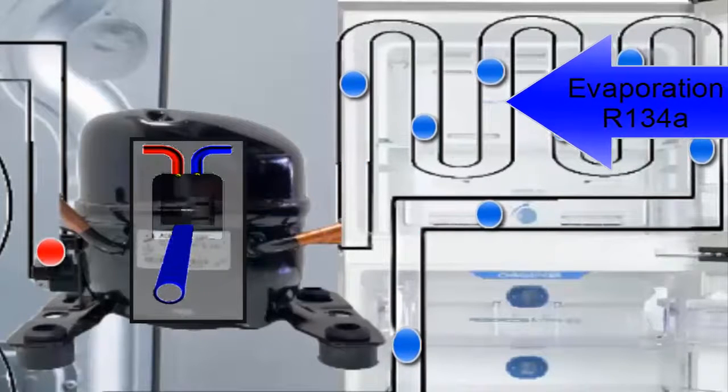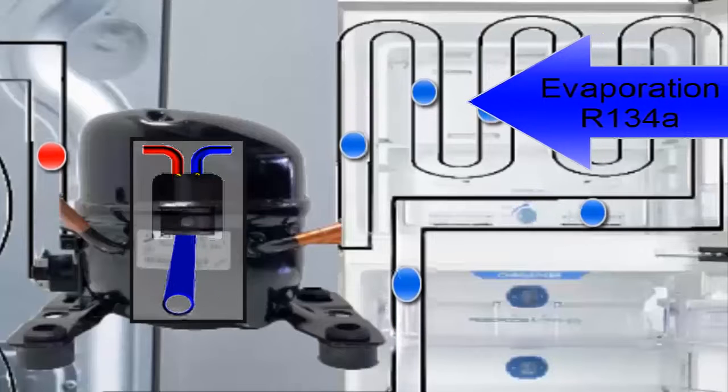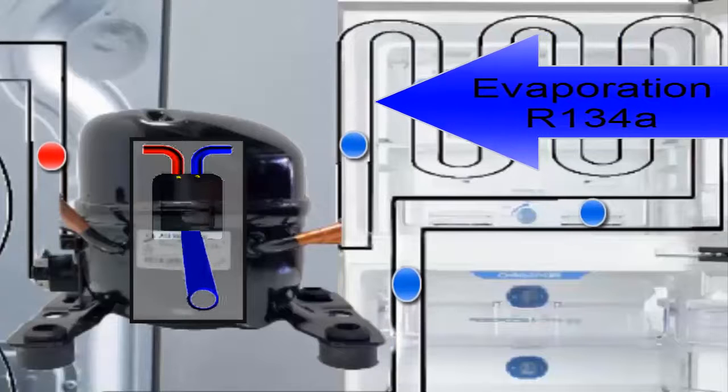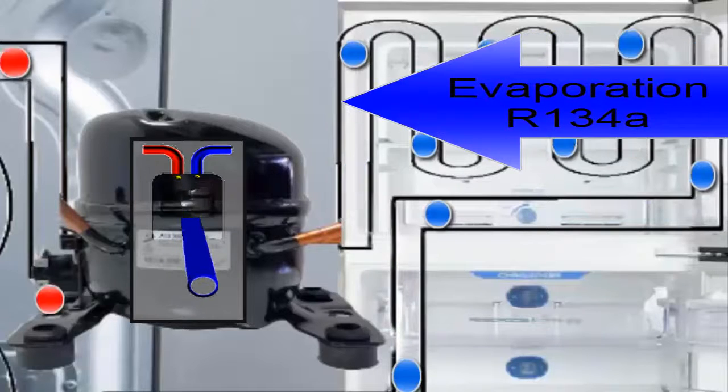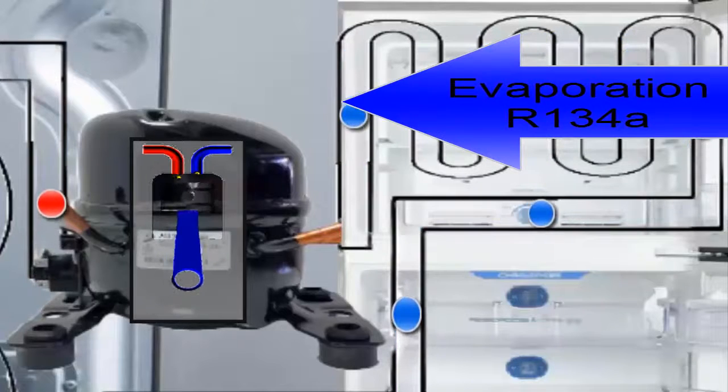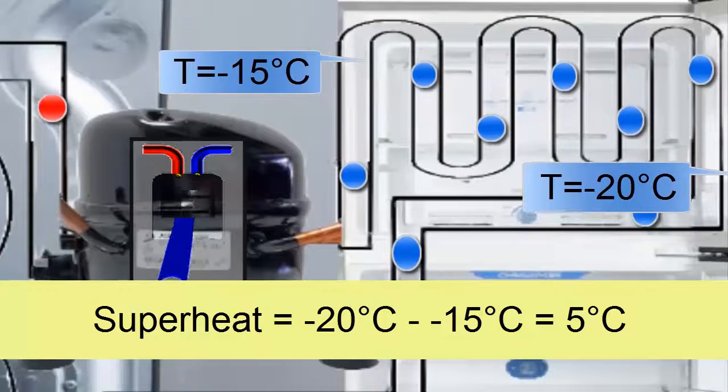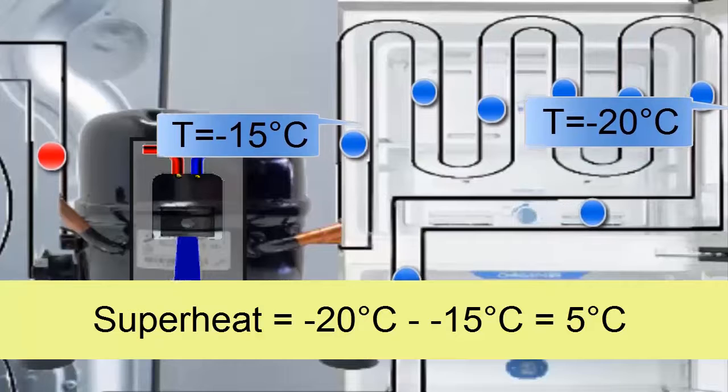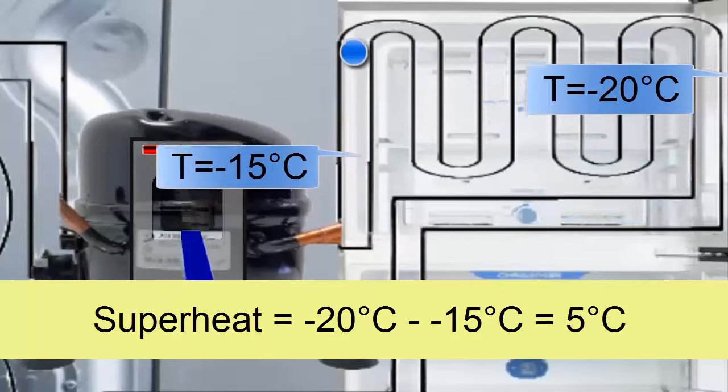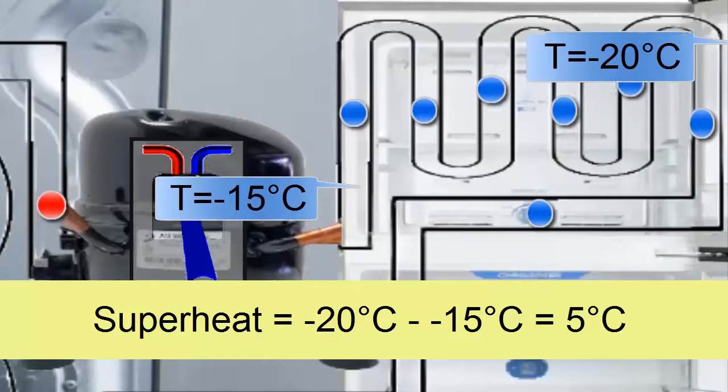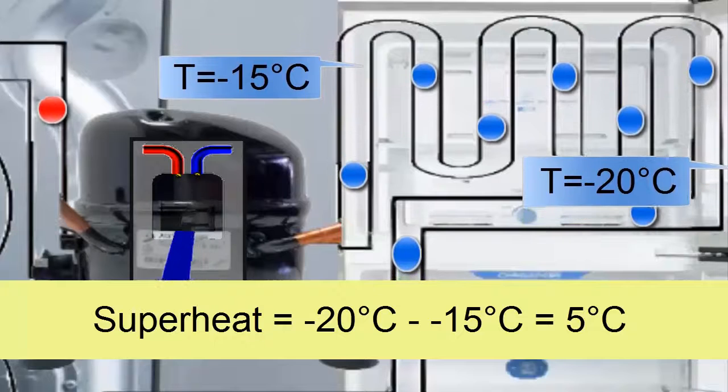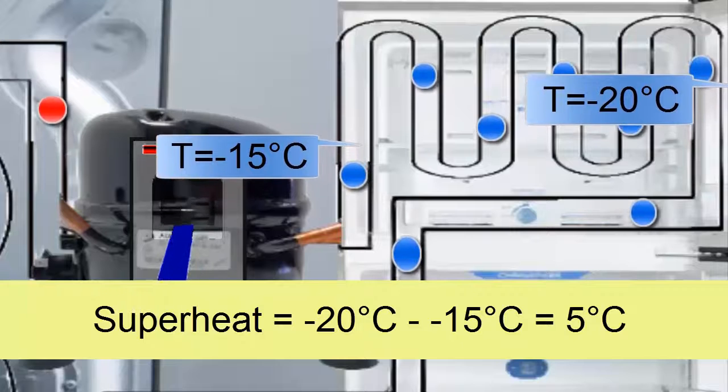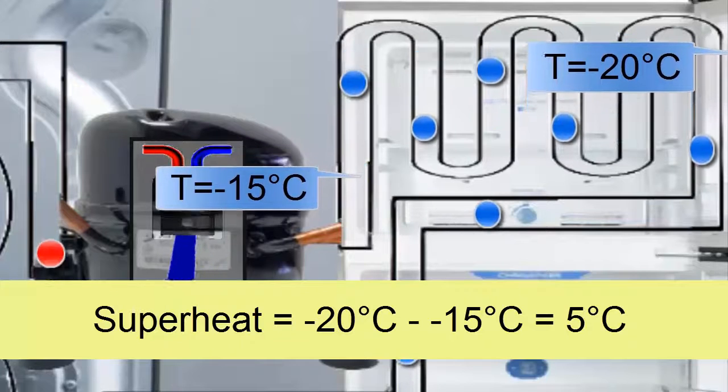The R134A, now in a gaseous state and with a slight temperature increase called superheating, is suctioned by the compressor. For this case, let's assume that the temperature of the R134A refrigerant in a gaseous state is minus 15 degrees Celsius. This means that the R134A refrigerant goes from minus 20 degrees Celsius to minus 15 degrees Celsius, so in this equipment, the superheating is 5 degrees Celsius.